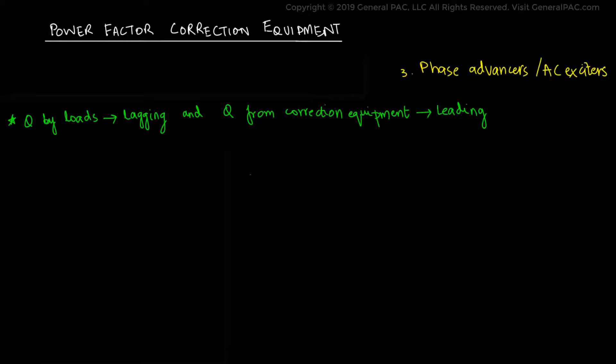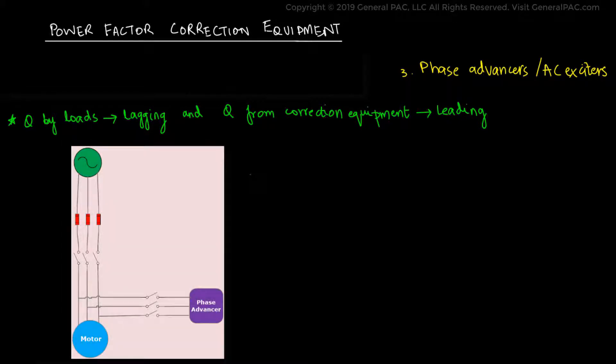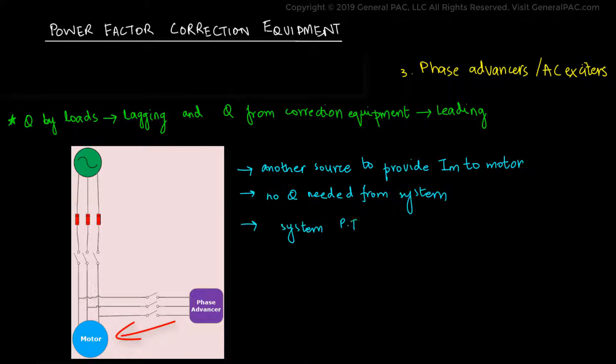Now, a third way to improve the power factor is to use a phase advancer. Since inductive loads like the induction motor operate by drawing reactive current from the system, what if we were to provide it with another source to provide the required reactive current? This is where phase advancer comes into play. It provides a reactive excitation current for the motors which relieves the system of any reactive power factor requirement and thus improving the power factor.